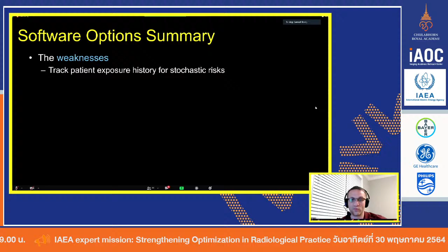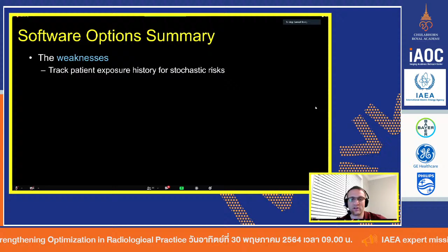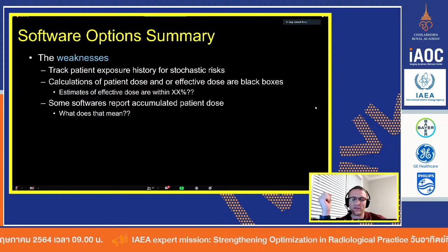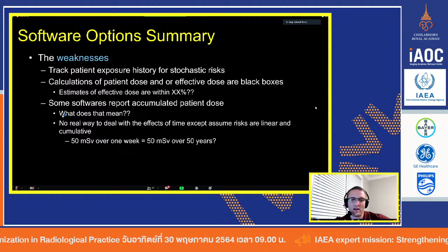Some of the weaknesses of this system is that, of course, it does not track true, defined risk, because it's not actual patient data. It's a close estimate, so we don't actually know what the stochastic risk is. I mentioned some of them are starting to accumulate the total patient dose, and I believe that's actually a bad thing, because the scan they got yesterday and the scan they'll get tomorrow are two different risk assessments. Just because someone's had 10 CT scans in their past doesn't necessarily mean they're at more risk tomorrow. There are a lot of variables that you need to take into account when you calculate overall risk. How they calculate an effective dose is somewhat of a black box. We talked about the two different ways.